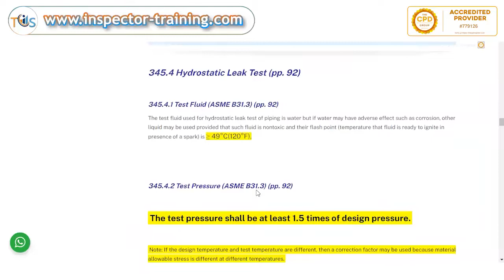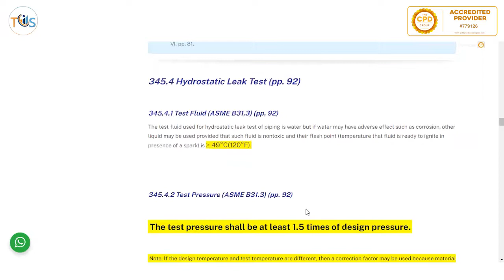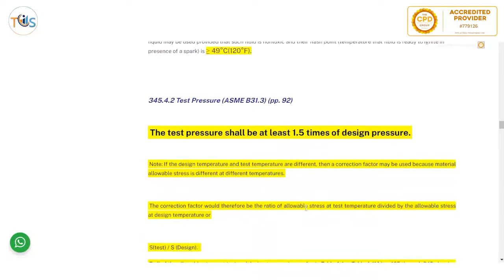Now, hydrostatic leak test. Test fluid used for hydrostatic leak test of piping is water, but if water may have adverse effects such as corrosion, other liquid may be used, provided that such leak test fluid is non-toxic and its flash point, that means the temperature that the fluid is ready to ignite in presence of a spark, is more than 49 degrees centigrade or 120 degrees Fahrenheit. So that is the requirement if you are not using water for test pressure. And the test pressure shall be 1.5 times the design pressure.